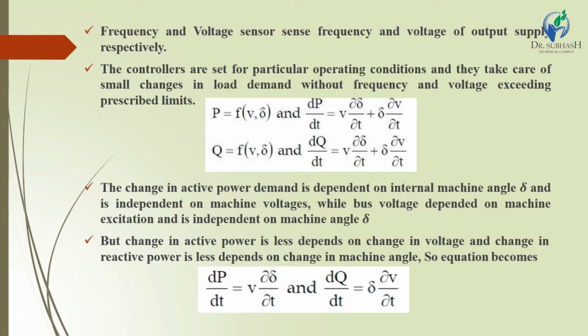In the case of an interconnected system, if the load demand changes are random, then both the frequency and tie line power are affected. The major function of the load frequency control is to minimize the transient variation in the frequency and tie line power with zero steady state error. If the real power changes, the system frequency changes, while if the reactive power changes, the voltage value changes. So we have to control both real and reactive power flow, but separately.